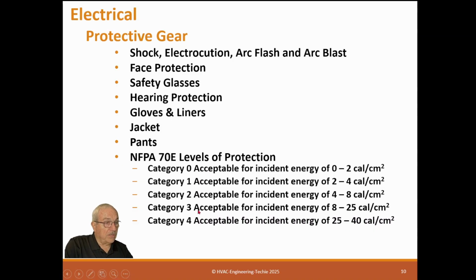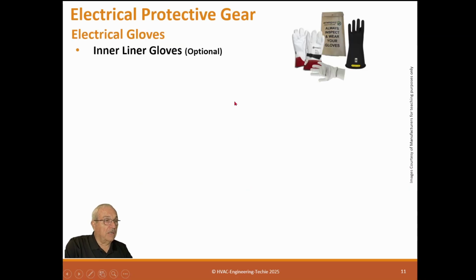These are the 0 through 4. There's a 0, but basically the 0 is nothing. So there's basically 4 categories of required PPE. And here's what they look like. So we have electrical gloves. Electrical gloves can have an inner liner. That's optional, actually, but if you're working in a real cold climate and you need gloves that actually insulate, then you put a liner on, and then you put rubber gloves, and the rubber gloves are the protective part for the power. The liner is for comfort, and then leather gloves on the outside are to keep from damaging the rubber gloves.